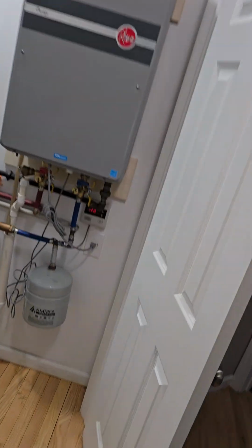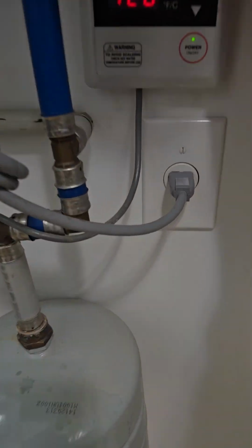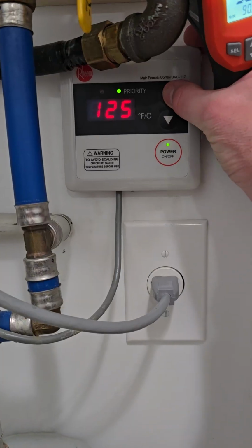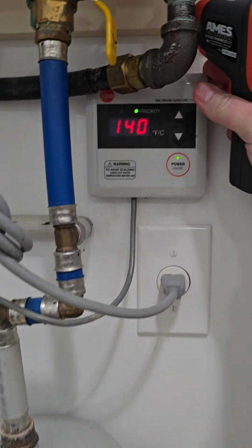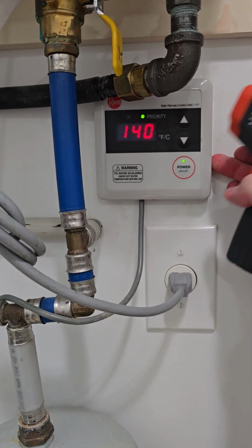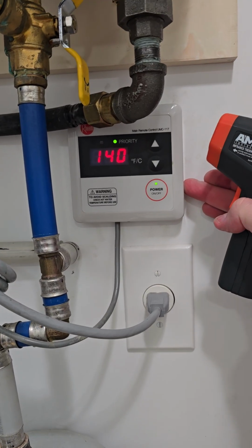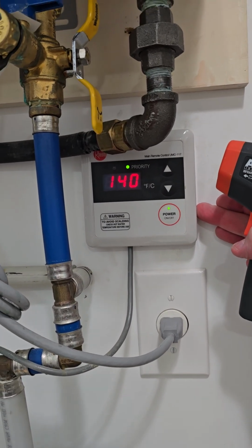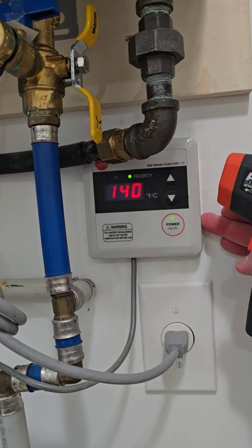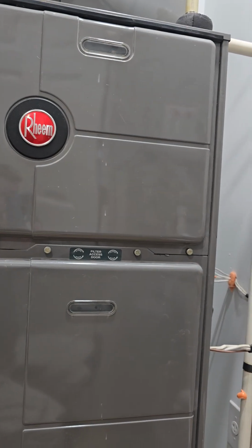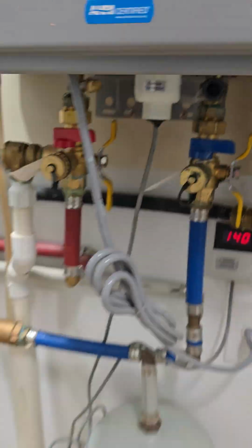We'll turn that off for a second and click this up to 140. Remember, this sensor, this temperature control, is not designed for the temperature of the water at the faucet -- it's designed for the water going into the heat exchanger, which then gets tempered so we don't scald ourselves.